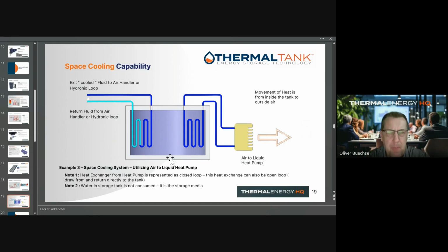How does that work? Yeah, so if you can picture two tanks, one where your hot fluid wants to be and the other one where your cold fluid wants to be, and sitting in between that is a liquid-to-liquid heat pump. So depending on what your process is doing, let's say you want to make chilled water, the energy flow is going to come out of the building into the buffer tank, in through the liquid heat exchanger that's extracting that heat and then pushing it into the hot tank. The hot tank, in turn, gives you the opportunity to utilize it in other processes in your building, such as a water preheat system, so that energy that would otherwise just get cascaded out into the atmosphere, you've reutilized in your process. So if you have a scenario where a consistent hot water need occurs in parallel with a consistent cooling need, you can get optimal energy leverage, essentially.